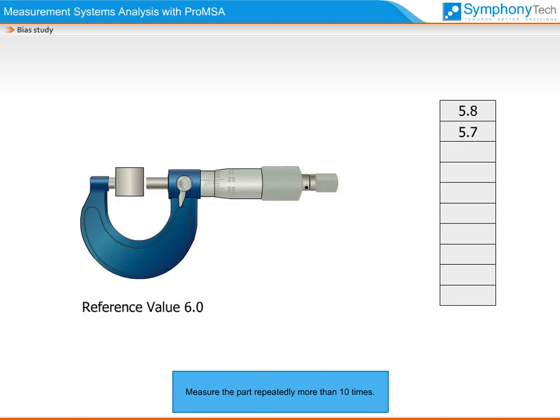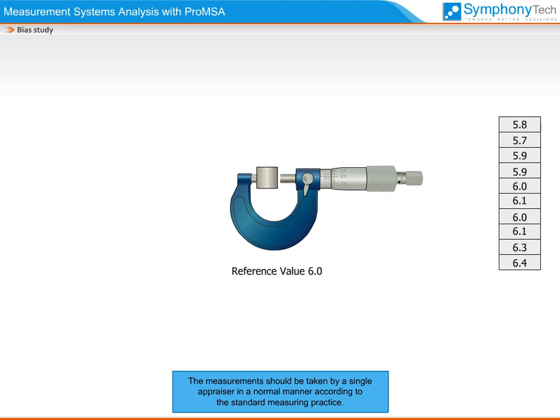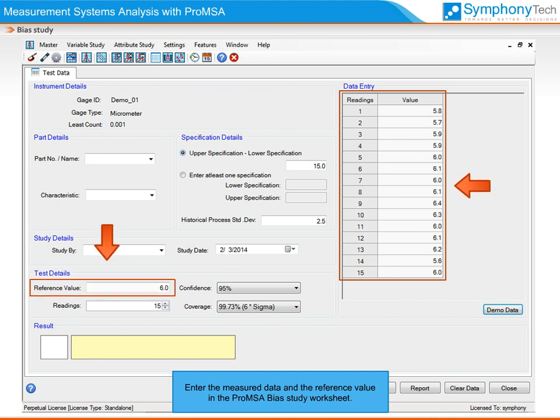Measure the part repeatedly more than 10 times. The measurements should be taken by a single appraiser in a normal manner according to the standard measuring practice. Enter the measured data and reference value in the Pro-MSA Bias Study worksheet.